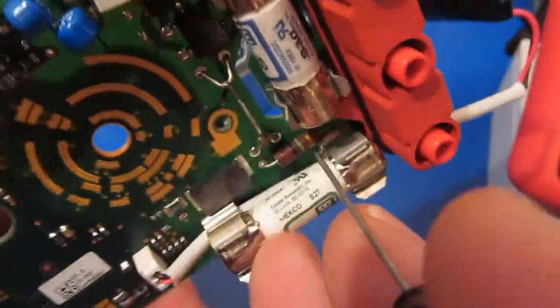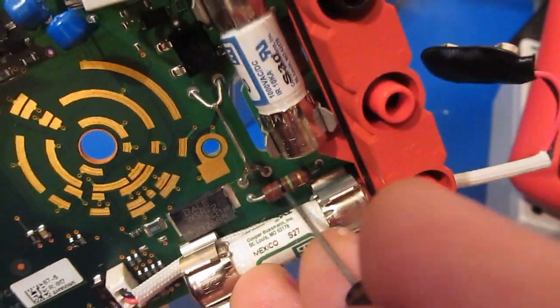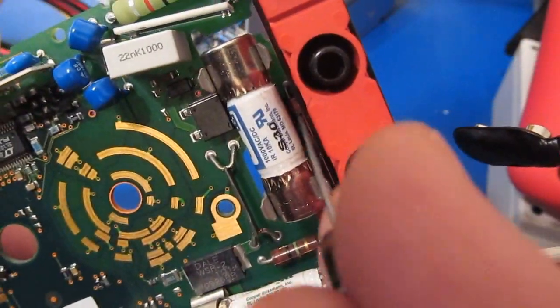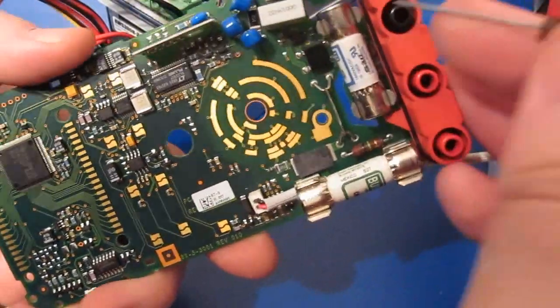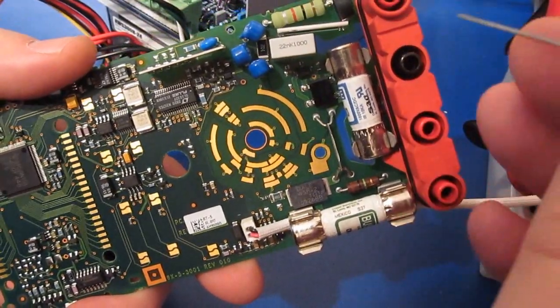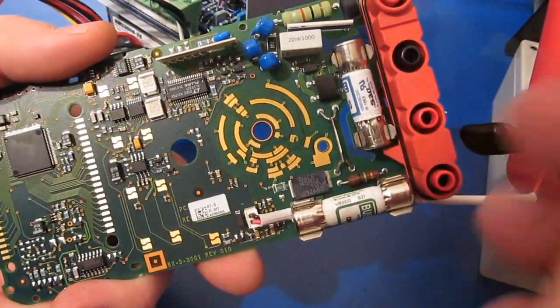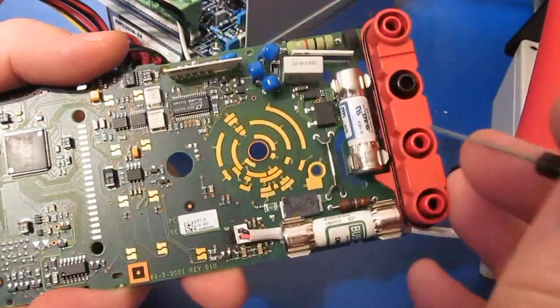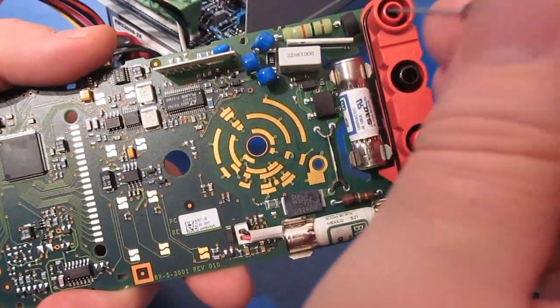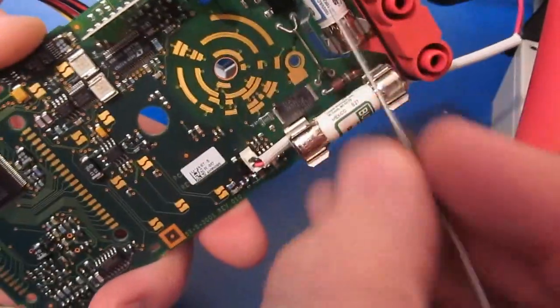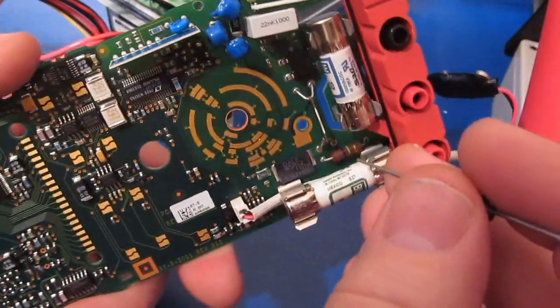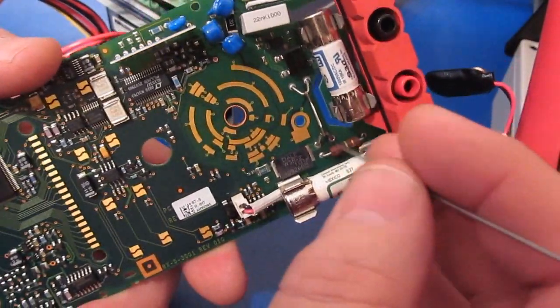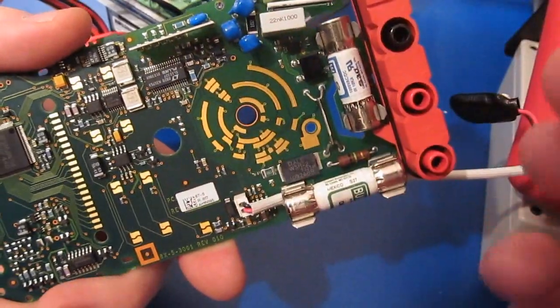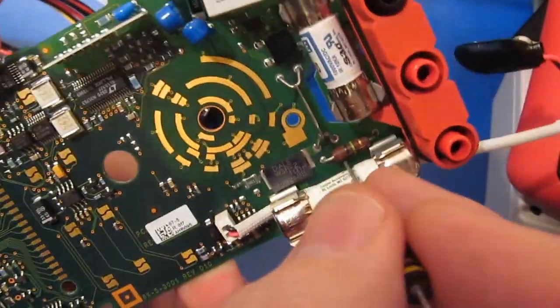One thing I did notice are these two resistors, this one here and the other one below the fuse. There's a test performed per the IEC standard where essentially you remove the fuses and apply a voltage that's 2 times over the maximum rating of the meter. What happened with the brand new meter is these two resistors got hot enough that you saw smoke coming out of the meter. Those appear to be a higher wattage part.